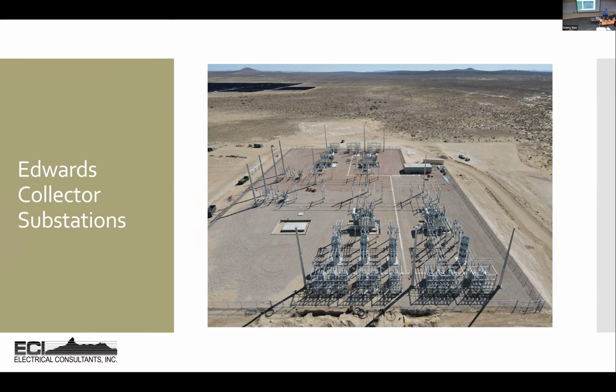So the collector substation is doing a lot of different things. It's collecting all the various circuits of energy from the generation field, which can be miles in length. It's also providing some current limiting support to prevent devices from suffering short circuit problems. We transform the voltage to the system voltage, meter it, and put protection devices on there in case of an accidental fault so we can trip the system.